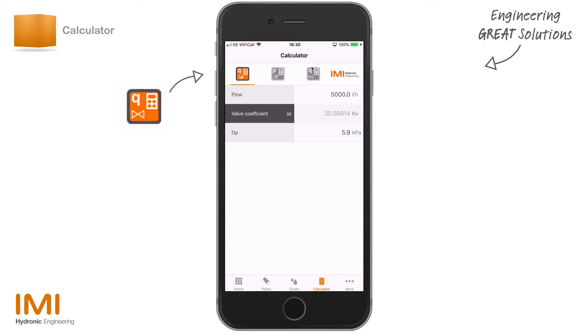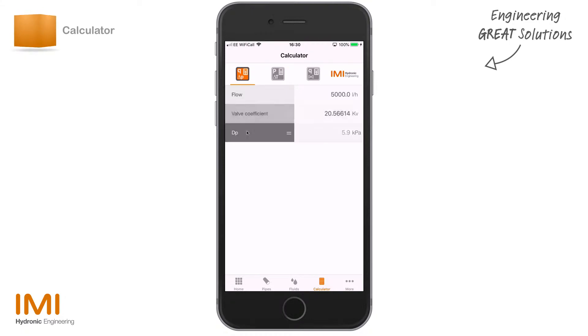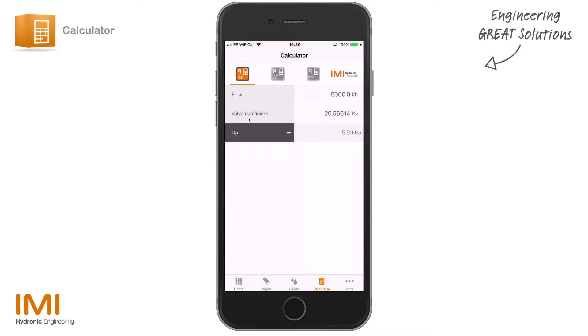The settings function is for the valve — pre-determining a setting for the valve, perhaps for a PIBCV such as a TA modulator or an STAD valve where you need a pre-setting for a specific pressure drop. Looking at the flow, valve coefficient, and delta P section: if you're looking for something specific — either flow, valve coefficient, or delta P — you simply tap on what you're looking for.